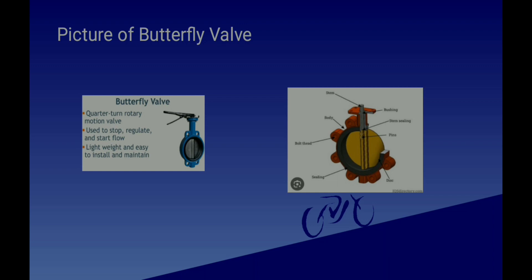In the second image we can see the parts of a butterfly valve. We have a stem, which connects the handle lever and the disk. We have stem sealing, which seals the stem and the disk. We have a disk that regulates the flow, and sealing to stop the flow and connect in the pipeline. Due to the quarter rotation the disk turns, regulating or stopping the flow. The disk is placed at the center of the valve and moves perpendicular to close or parallel to open the flow.